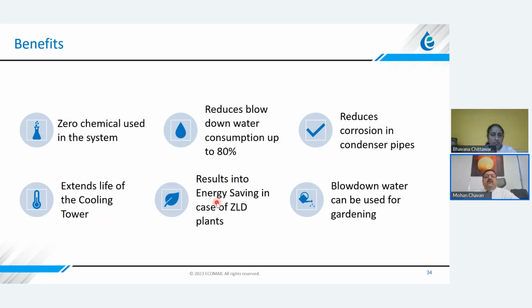It results in energy saving. Now, you must have seen in many industries, or even for buildings nowadays, there is a requirement of zero liquid discharge, or at least we have to treat the water, and you just can't let the water down like that into the drain. So there is a lot of energy cost involved in ZLD plants. Once we save the blowdown water consumption, ultimately there will be a saving in the energy cost. And the blowdown water can be used for gardening because there are no chemicals in the blowdown water. So in fact, truly you can achieve ZLD if you have a garden there and the water is required for gardening.